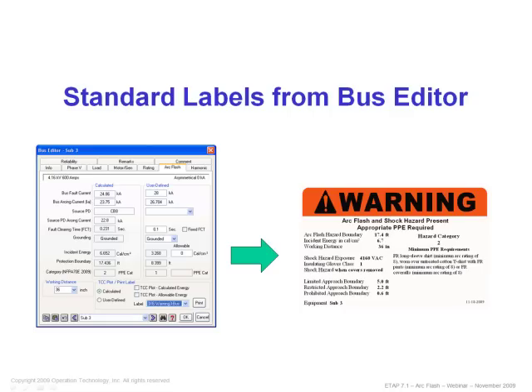Standard labels can be created from the bus editor. By going onto your one-line diagram and double-clicking on a bus, you can navigate to the ArcFlash page. From there, there's a section called TCC Plot slash Print Label. There will be a drop-down menu on the bottom right-hand corner, which will indicate the size and the template you'd wish to print. To the left of that feature, there are two radio buttons, one for Calculated and one for User Defined. Please note, when selecting Calculated, the results listed in the Calculated section of this window will be printed on the label, and vice versa, if the User Defined radio button is selected, then the User Defined results will be printed onto the label.